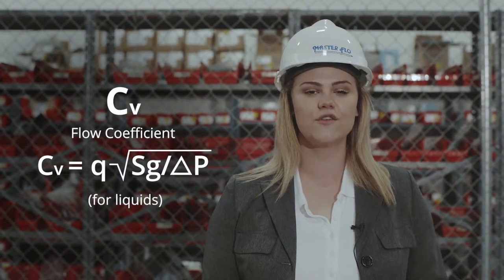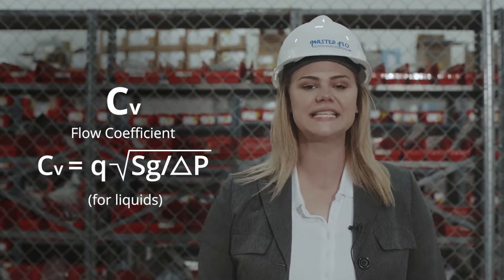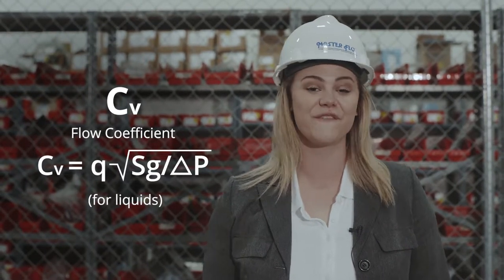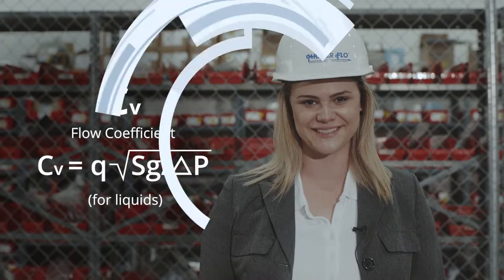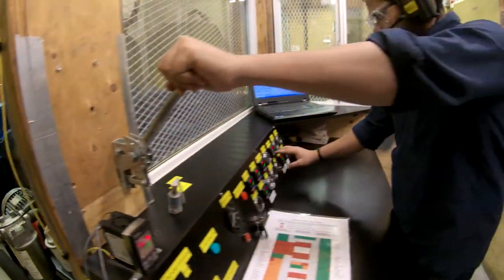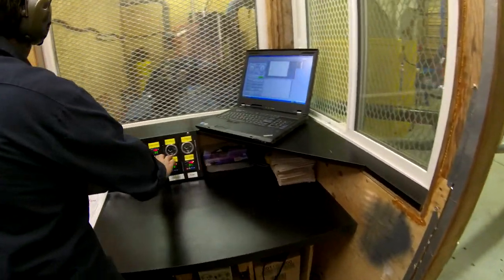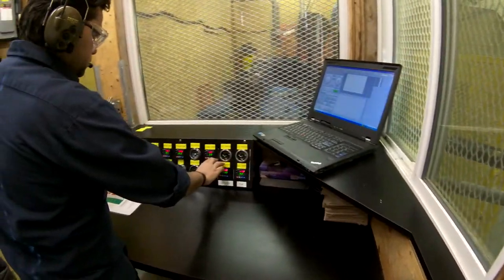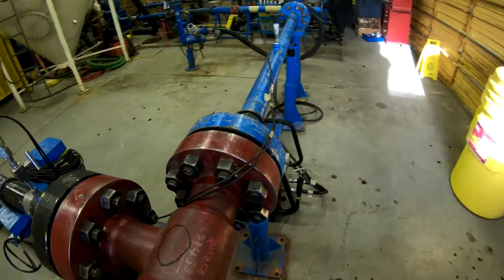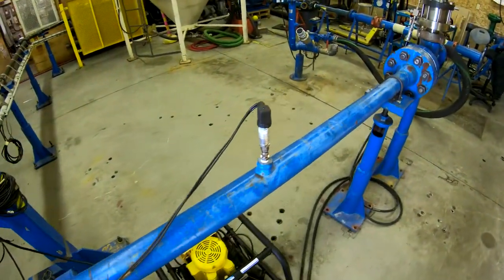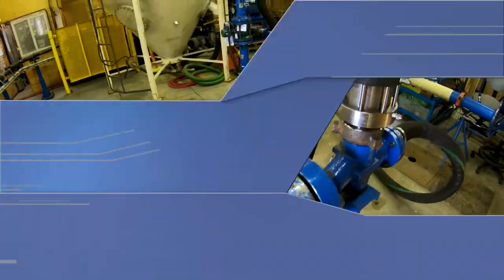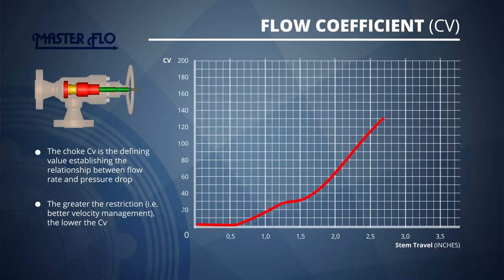To compare valve capacities and to size valves for specific applications, several coefficients are used. The first is the flow coefficient. Flow capacity testing establishes a flow curve over the valve travel and provides a basis for comparing trim styles. Each valve type has a unique curve based on internal geometry. A greater restriction provides better velocity management, but lowers the flow capacity.